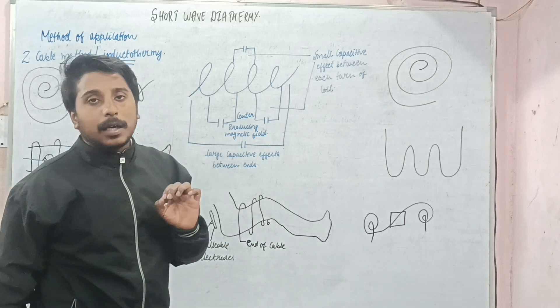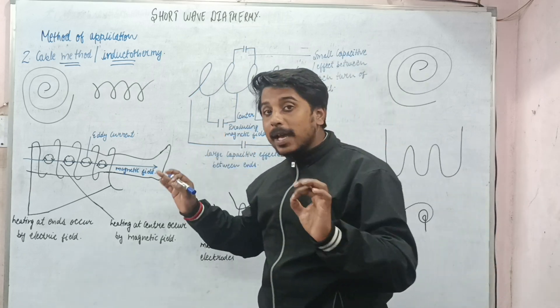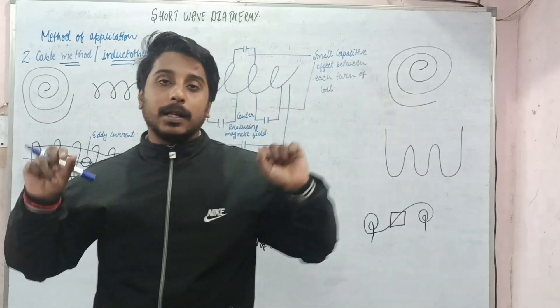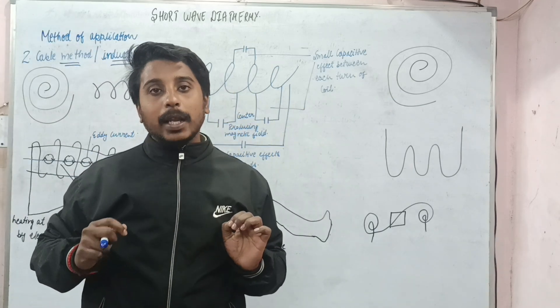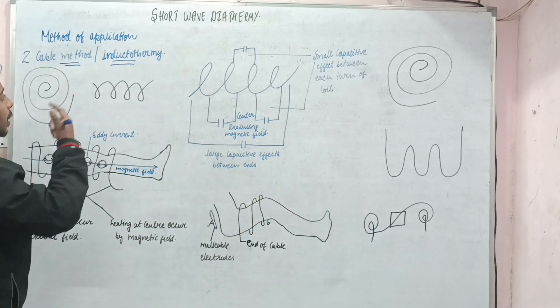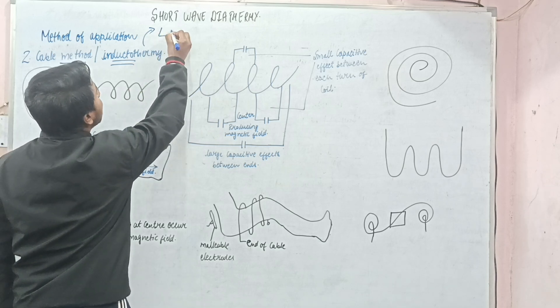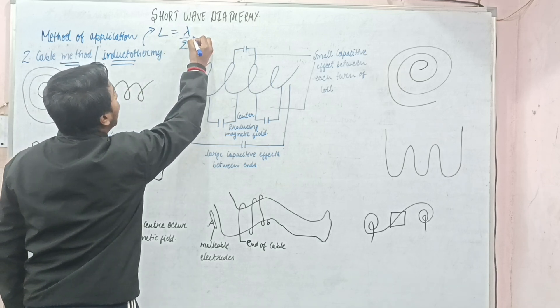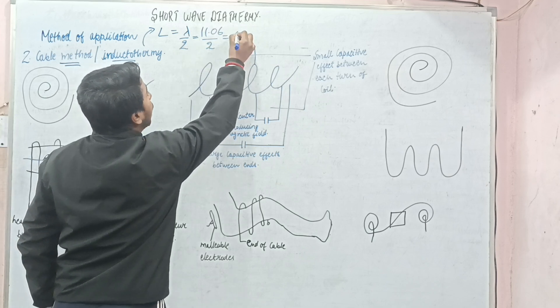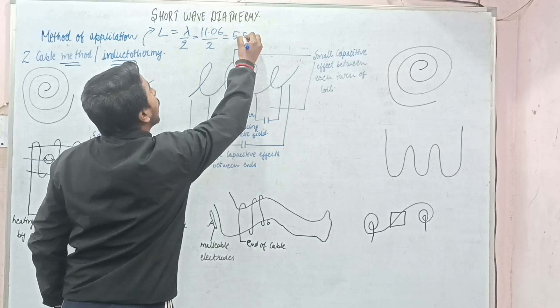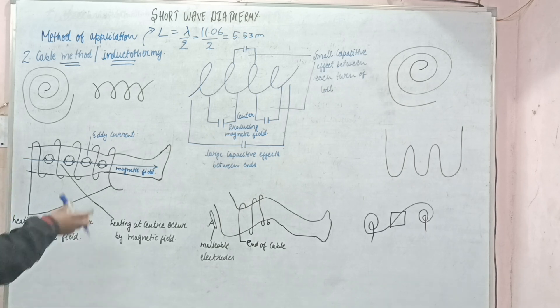It is one of the most commonly used methods of SWD application. Here we use a cable, which we wrap around the body part like a spiral, and then we apply the shortwave diathermy. Its length is half of the wavelength. The wavelength of SWD is 11.06 meters, so its half becomes 5.53 meters — this is the length of the cable.